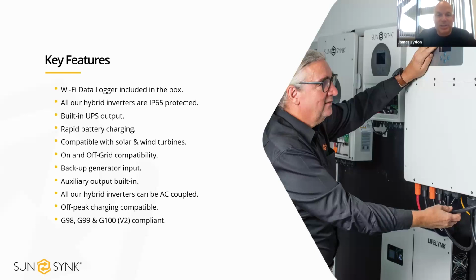Off-peak charging compatible as standard. So you've got, as standard in the inverter, 6 different time periods where you can set when you want to charge the batteries from the grid or discharge the batteries to the grid, depending if there's a session with one of the energy providers. And we've got full compliance, so G98, G99, and G100 V2 on all of our inverters.